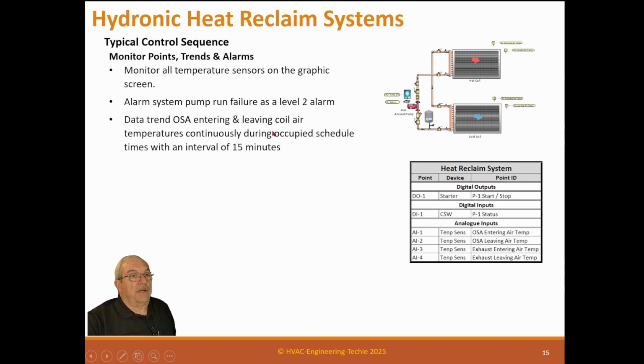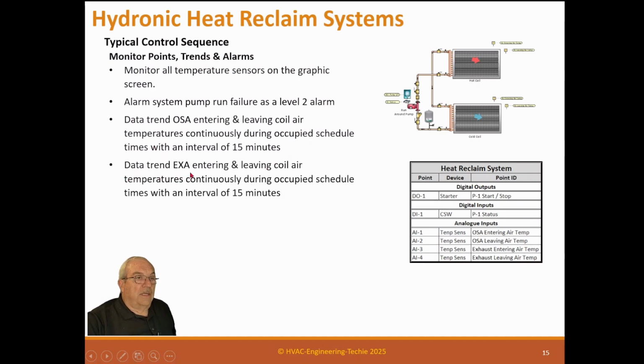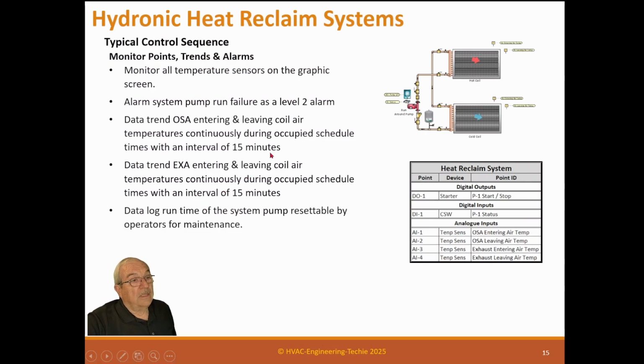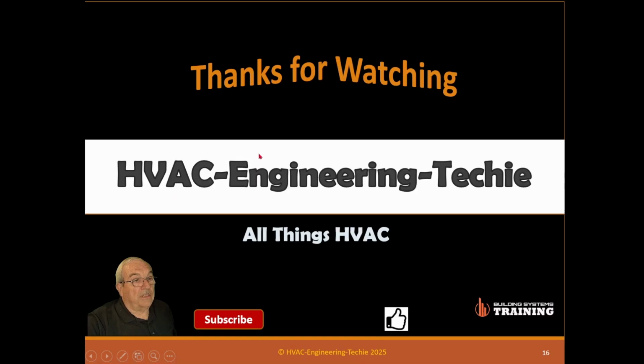Data trend outside air entering and leaving coil temperature continuously during occupied scheduled times with an interval of 15 minutes. Data trend the exhaust air entering and leaving coil temperature continuously during occupied scheduled times with an interval of 15 minutes. And the operator will use these to see if the sequence is actually working right. You can watch it and say, well, it's greater than 8 degrees differentially, it should be working. Data log runtime of the system pump, resettable by operators for maintenance.